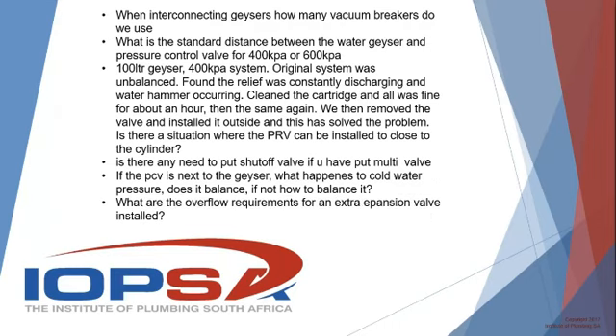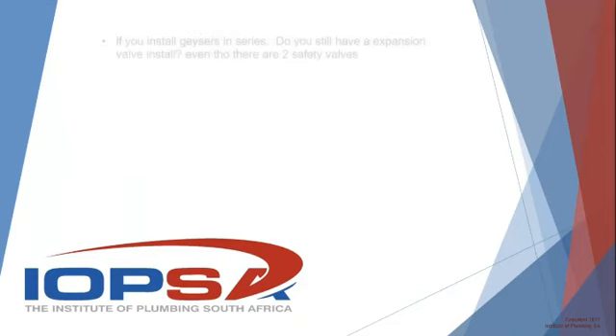Okay, so this question pertains to an extra overflow, well, the expansion valve situated close to the geyser, presumably in a situation where you have the PRV somewhere. Then you have a mandatory shut-off valve close to the geyser, and because of that, you'd now need to install an additional relief component between that valve and the geyser. And the question is, what are the overflow requirements for that expansion valve? I think I'm right in saying that it is exactly as per a normal expansion relief overflow would be. Yes. Exactly. SANS doesn't specify if it's a second one, it changes. It stays exactly the same.